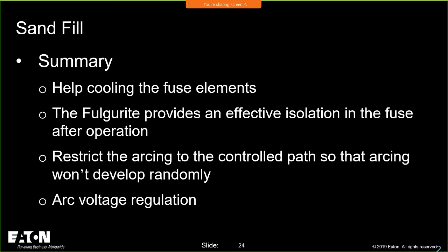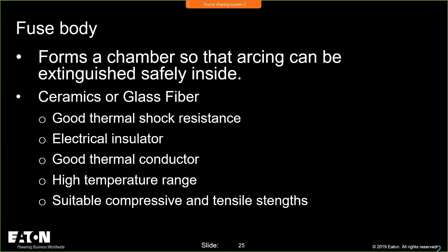And you saw both a created image and then an actual picture of what it looks like after one's opened. And again, the fill restricts the arcing to the controlled path. So you want to make sure that those little arc flash events that are happening inside of that enclosure, that tube, are controlled and held in that path. And then again, it regulates that arc voltage. So the sand plays a strategic role inside of that element, inside of that device.